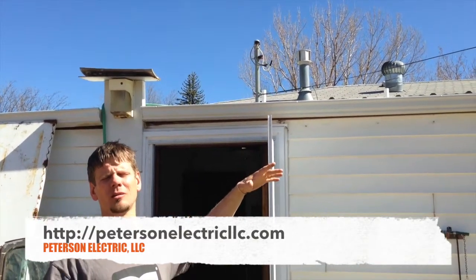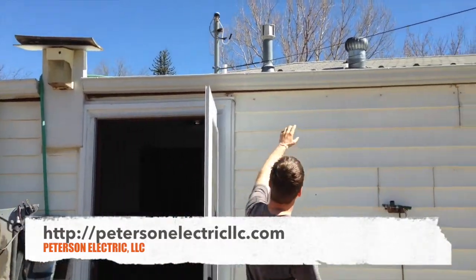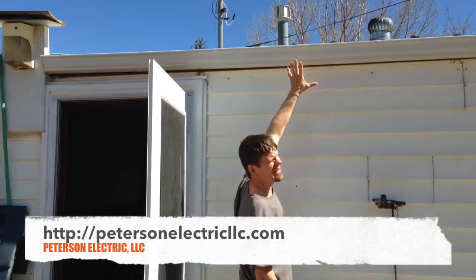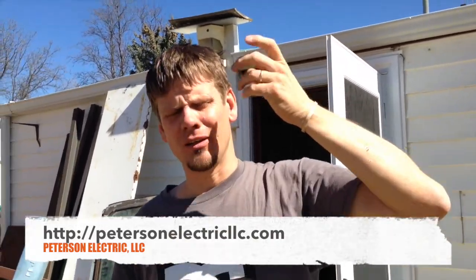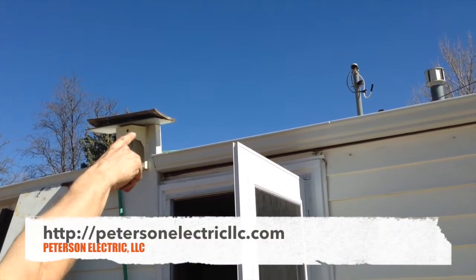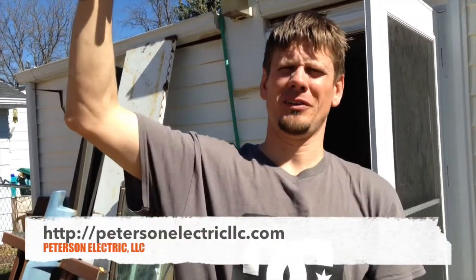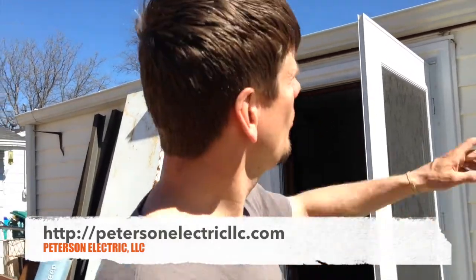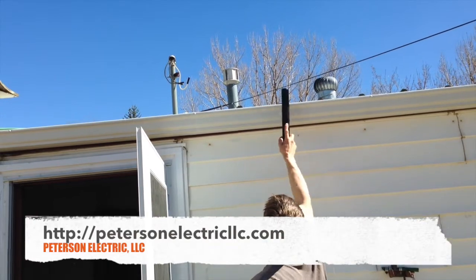It talks about not having any drip edges above the gutter or any gutters above the panel, and it could also be around 110.26 talking about accessibility to a service. With the meter outside, this gutter goes up only to about eight feet, maybe seven and a half. The NEC code talks about ten feet minimum for drip loop splice connectors — you can see the splice connectors, drip loop, service mast, and weather head up there — but some power companies request twelve feet, so you have to adhere to the highest requirement.